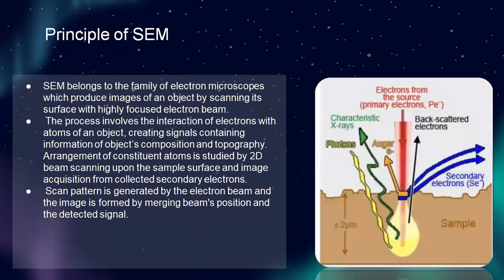Principle of scanning electron microscope: incoming electrons can be reflected or backscattered from a bulk specimen and can release secondary electrons. Primary electrons are focused into a small diameter electron probe that is scanned across the specimen. Electrostatic or magnetic fields applied at right angles to the beam can be used to change its direction of travel. By scanning simultaneously in two perpendicular directions, a square or rectangular area of specimen known as a raster can be covered. An image of this area can be formed by collecting secondary electrons from each point on the specimen.